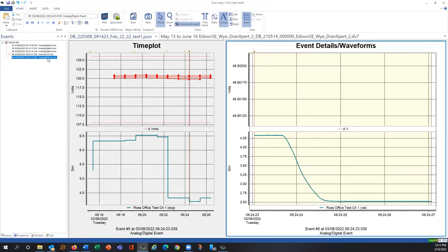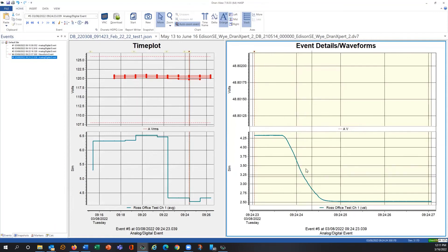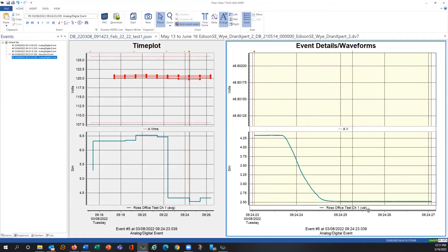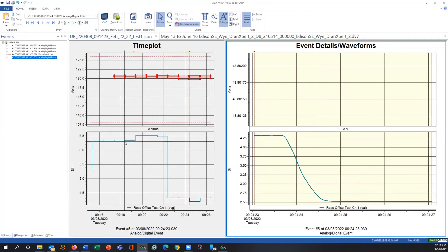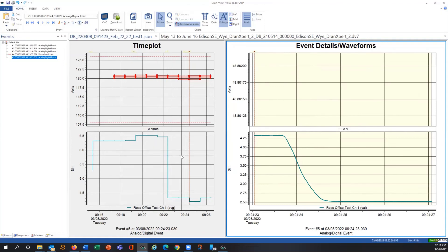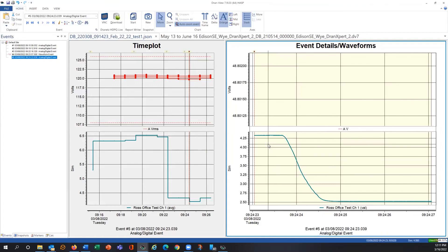You can see additional RMS events and transducer input events here. I basically triggered as the input went down — I think three and a half volts was my trigger point — and you can see pre and post trigger on that. So you can not only journal the transducer inputs over time, but you can also trigger on high or low limits. Those triggers are set up in the units of those particular transducers.